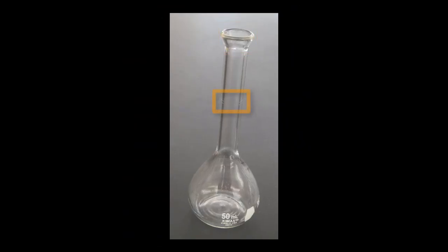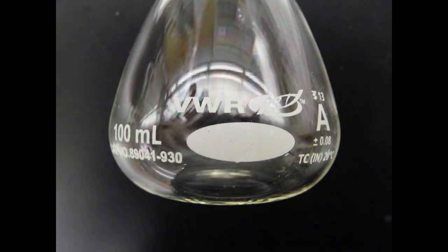The calibration mark is located on the stem. Important information is recorded on the bulb of a volumetric flask, such as the volume contained in the flask, the uncertainty of the volume contained, and the class of glassware. Volumetric flasks are available as Class A or Class B. Class A glassware is more accurate versus Class B glassware.